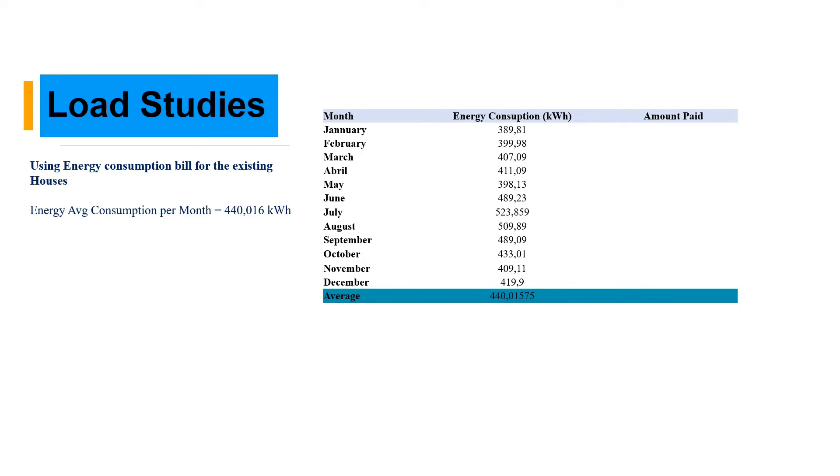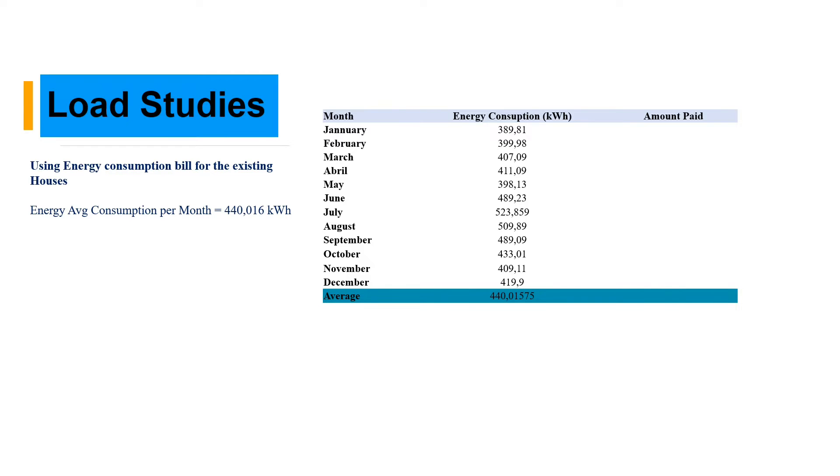It's added 20% of losses or additional appliances that might be added in the house. The second step is using an old house. An old house normally comes with an electricity bill from the utility power supply. It gives you monthly energy consumption and the amount you need to pay. Here you can get the average monthly, which is 440 kilowatt hour per month, then divide by 30, which gives us an estimation of daily consumption, which is 14.667.